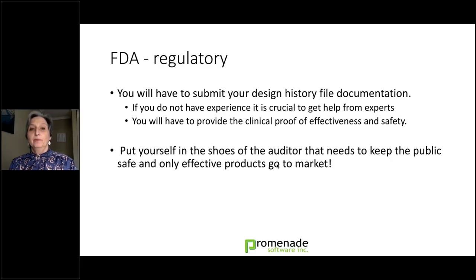When you go to the FDA, the regulatory, you will need to submit your entire design history file, documentation that's part of that. If you don't have experience with that, it is crucial you get help from the experts, because there's a lot that goes into it. A lot of pieces, a lot of small pieces that need to be covered. Often a lot of those are not difficult. I think I've covered the big pieces, the requirements, the design, the risk analysis, and the verification. But there's a lot of small pieces that need to happen as well.